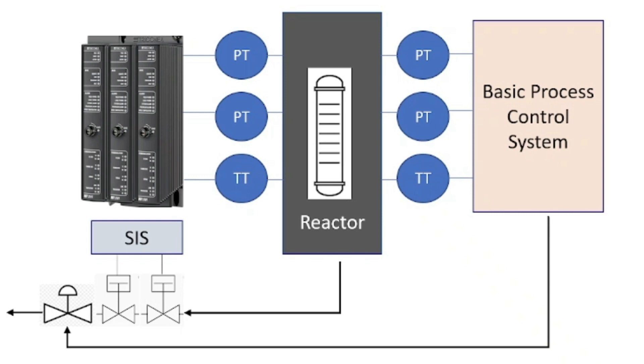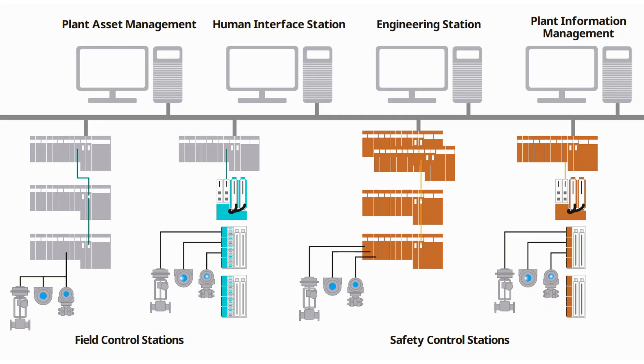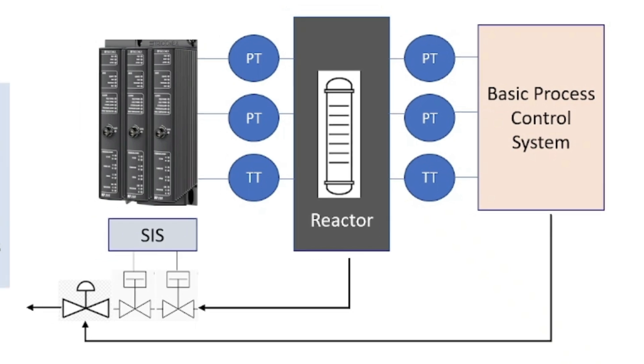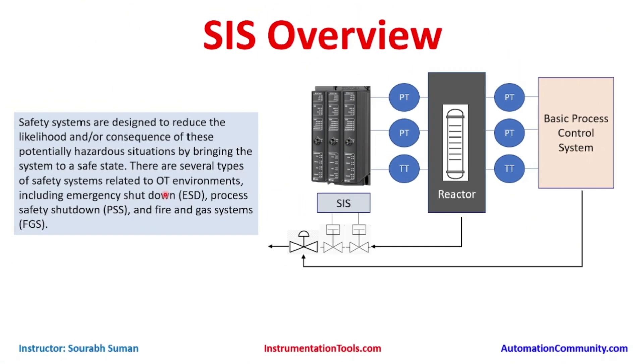The main responsibility of these controllers is to bring the system to a safe shutdown in a controlled manner, not in an abrupt manner. SIS are typically independent from all other control systems, so that failure of the Basic Process Control System (BPCS) will not impact the functionality of the SIS. Initially, SIS were designed standalone, physically and logically separated — sometimes air-gapped. Organizations are again going for air gapping in some places due to increasing cyber threats from connected networks.